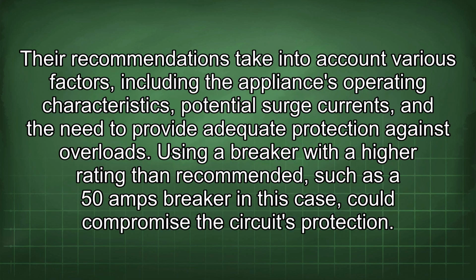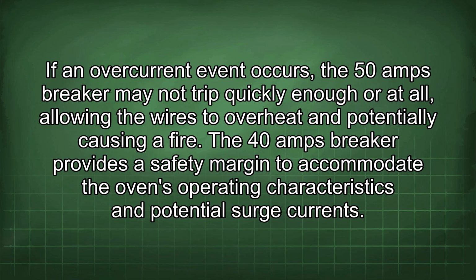Their recommendations take into account various factors, including the appliance's operating characteristics, potential surge currents, and the need to provide adequate protection against overloads. Using a breaker with a higher rating than recommended, such as a 50 amps breaker in this case, could compromise the circuit's protection. If an overcurrent event occurs, the 50 amps breaker may not trip quickly enough or at all, allowing the wires to overheat and potentially causing a fire. The 40 amps breaker provides a safety margin to accommodate the oven's operating characteristics and potential surge currents.